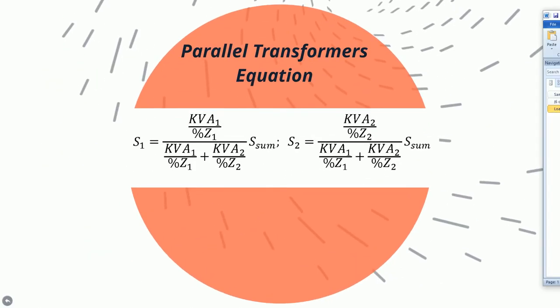In order to solve this problem, I recommend using the following equation, which can only be used when two transformers are arranged in parallel. This can work for differing kVA rated capacities and differing percent impedances, as is given in this problem. This equation states that the power flow through a certain transformer, whether Transformer 1 or Transformer 2, is proportional to the rated power of that transformer and inversely related to the percent impedance of the transformer.